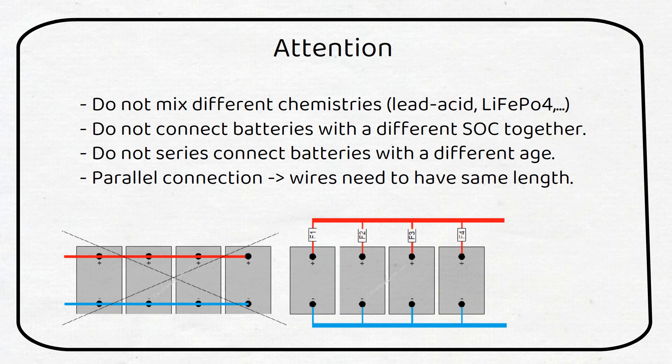Every parallel battery should have a fuse installed. For lead acid this can be an ANL fuse. For lithium it can be a circuit breaker, class T fuse or a rail mount fuse which is more popular in Europe. All of these have a high current breaking capacity. If one battery were to fail it will not deliver current to the other battery.